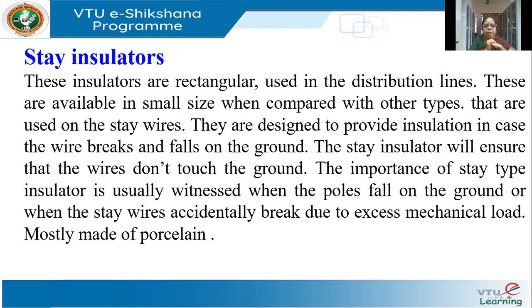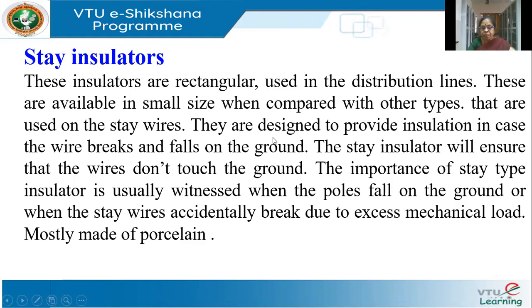The other type of insulator are stay insulators. These are normally used for lower voltage lines and they are rectangular in shape, used in distribution lines. Their size is small and they are used to provide insulation to stay wires. Stay wires are the wires connected to the poles to hold them firmly and give them mechanical strength. These stay insulators are designed to provide insulation in case the stay wire falls to the ground.